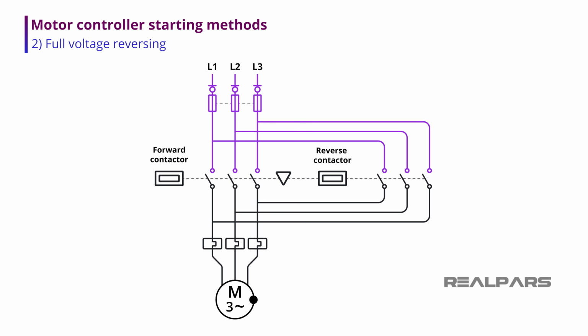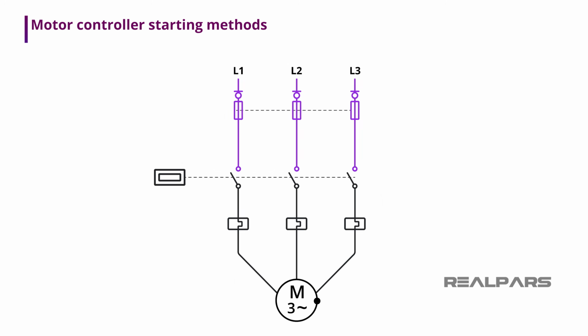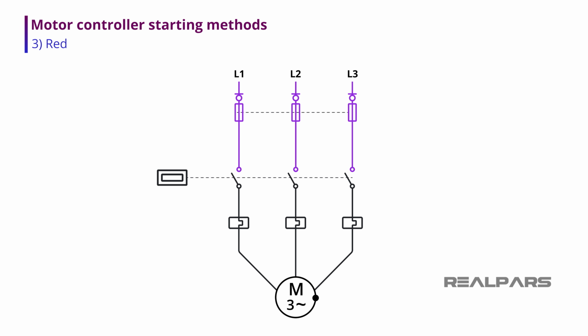In a full-voltage reversing motor controller, the controller has two separate actuating states, one to operate the motor in the forward direction, and one state to allow the motor to operate in the reverse direction. This is accomplished by adding a second contactor. The forward contactor acts the same as in the FVNR, and the reverse contactor swaps the position of two of the phases. This reversal of two phases causes the magnetic field in the motor windings to be reversed, causing the motor to spin in the opposite direction. Special physical safeguards are in place to prevent the actuation of both contactors at the same time, which would be very damaging. The third type of motor starting method is called reduced voltage starting.